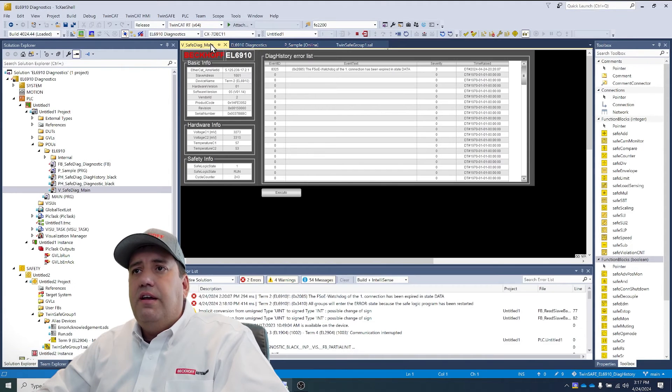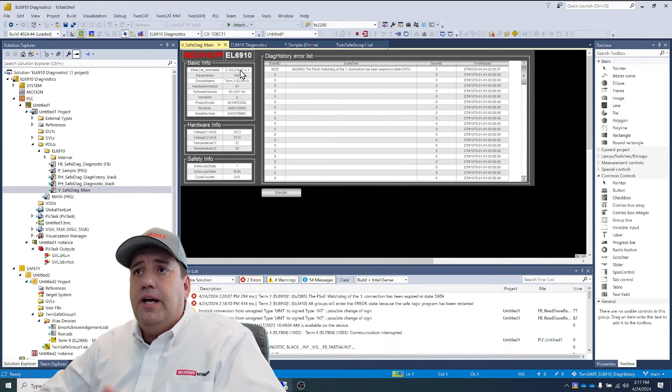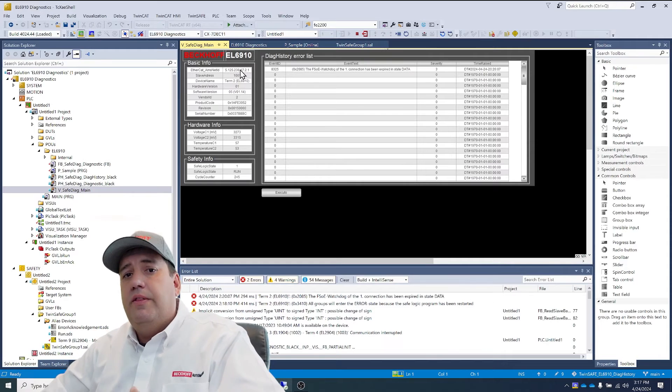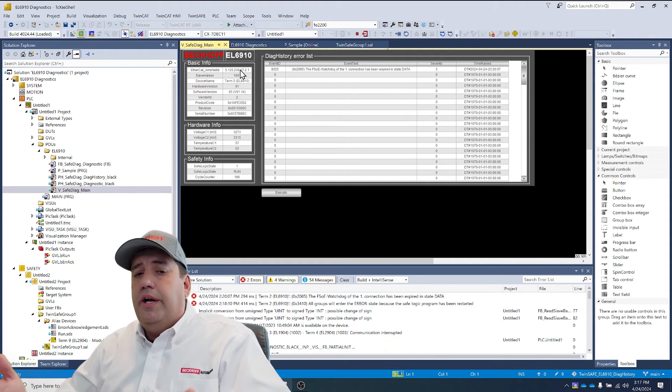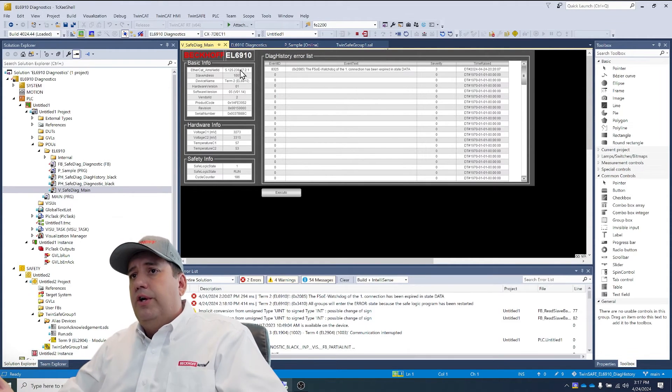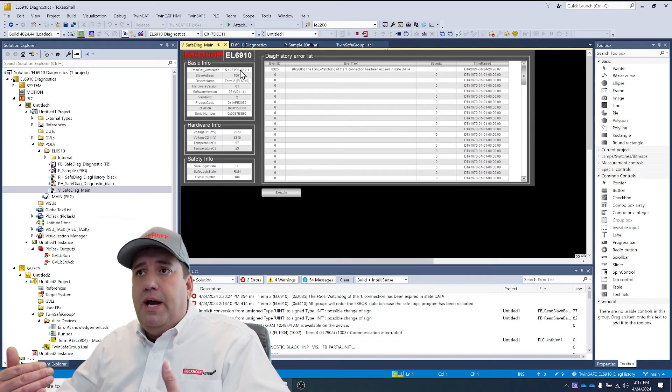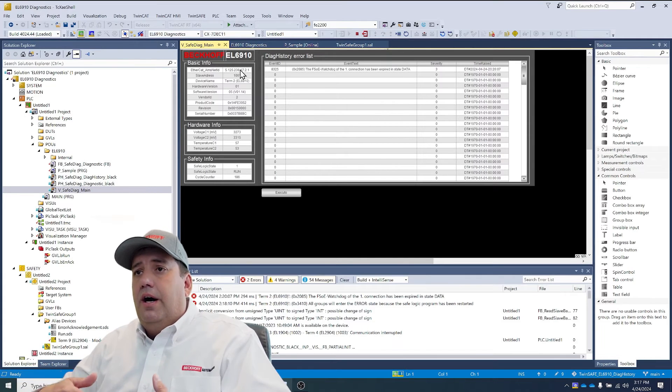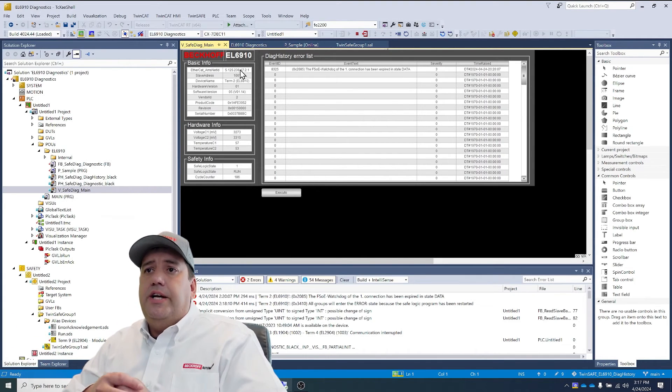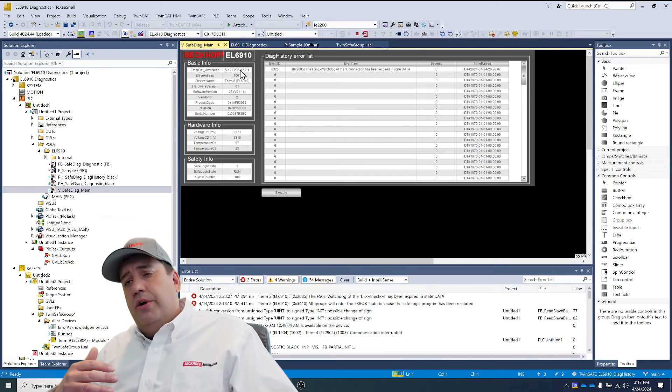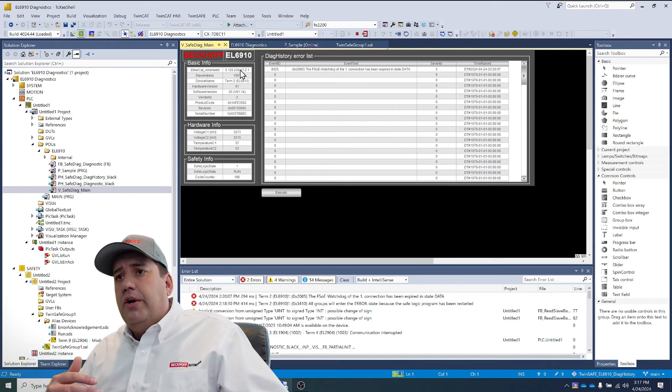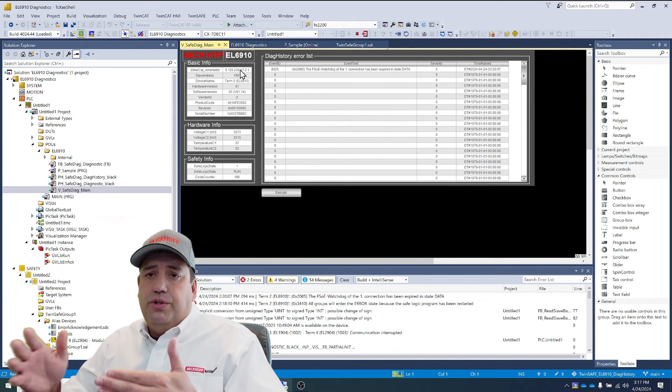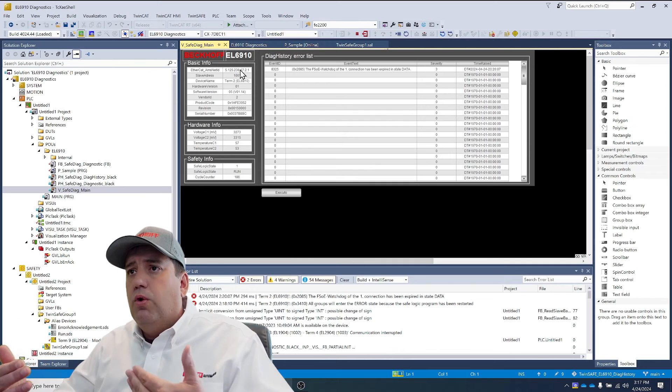Now, if we look at the visualization, we start to see real data. It now says EL6910 rather than the EL2911. Like it said earlier, we're getting real information back in the basic info, like revision numbers, serial numbers, things of that nature. We're seeing the temperatures that are so important to monitor. And then the state of the actual device itself that currently we're in run.